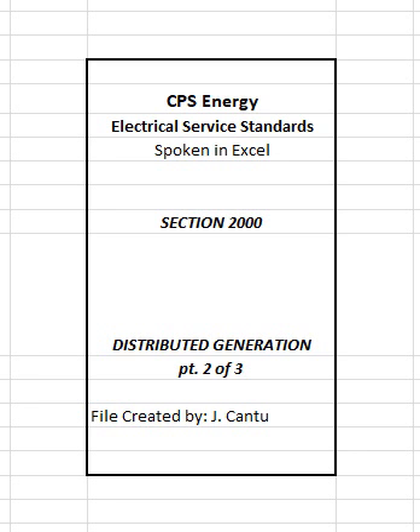A. Protection and coordination. Customers' DG facilities shall be designed with listed equipment and protective hardware and software designed to prevent connection to de-energized CPS Energy circuits. Customer shall also be responsible for protecting DG equipment in such a manner that CPS Energy system outages, short circuits or other disturbances, including zero-sequence currents and ferroresonant overvoltages, do not damage the customer's DG equipment. Note: surge protection required as outlined in Figures 2002 and 2004.